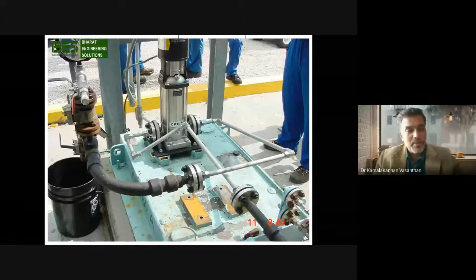Will anyone be able to see where the pump suction and delivery are here? Here is the suction, and here is the delivery. With just a small alteration of these inlet and outlet pipelines, these multiple bends, 1, 2, 3, 4, 5, 6 bends, would have been reduced. This inline pump is manufactured in such a way that not even a single bend is required in the pipelines. The more bends you have, and the more pipeline length or vertical height you take, the more loss to the system. It took a mere 2.5 hours to rearrange these pipelines, and this pump is still running fine as on day 2.